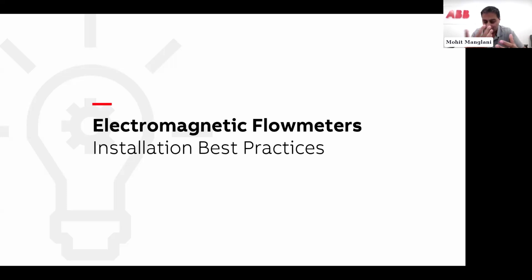Just to circle back, mag meters have been around for a long time, and there are still flow tubes out there that are 50, 60 years old that are still working. The life of the electronics has actually been bypassed compared to the flow tube. So if you're having troubles out in the field, these best practices are some things you can look at, maybe improving the performance or the accuracy of what you have.